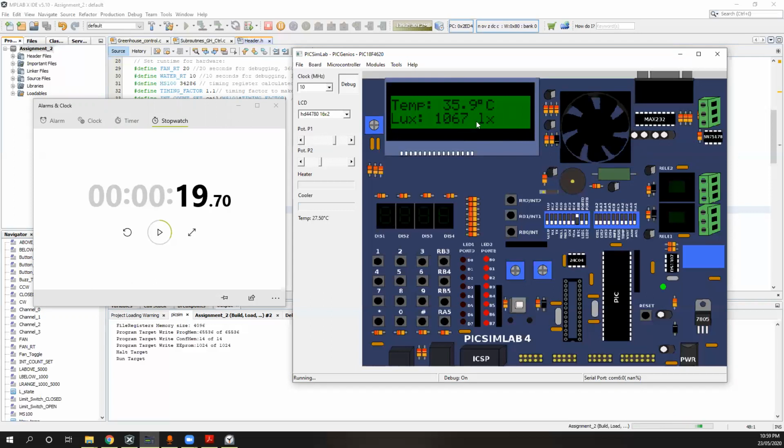There you go. All right, the other thing as well is if we turn it on and then, after the sprinkler stops, say for example it falls back below the 36 degrees, or the sprinkler's on, the fan shouldn't turn on. All right, so notice the fan did not turn on this time because it was below the 36 degrees. So that's met that requirement perfectly.